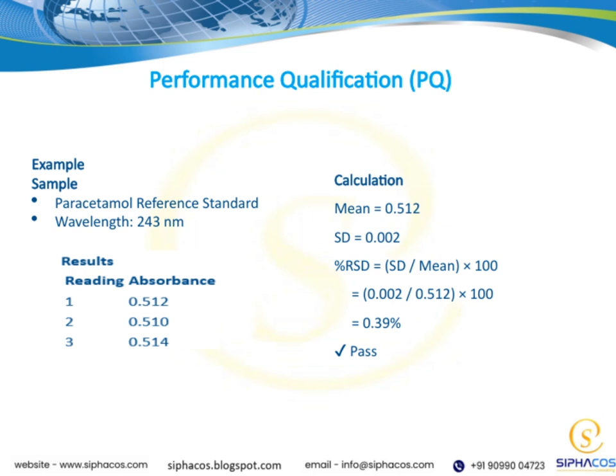Now, to evaluate the precision of our measurement, we calculate the percentage relative standard deviation, or percent RSD. This is done by dividing the SD by the mean and then multiplying by 100. So we take 0.002 divided by 0.512, which gives us approximately 0.0039, and then multiply that by 100 to get 0.39%. Seeing a percent RSD of 0.39% indicates very good precision, meaning our measurements are consistent. The slide also marks this as a pass, confirming that our method meets the required precision criteria.